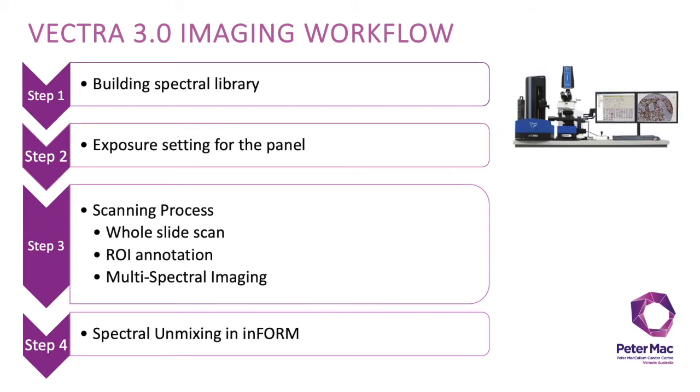The second step is to set the exposure settings for each of your slides. The Vectra 3 microscope then performs a low resolution whole slide scan. After selecting the regions of interest using Phenochart, the slide is re-scanned at high magnification to acquire the multispectral images. And the last step is to perform the spectral unmixing in InForm.